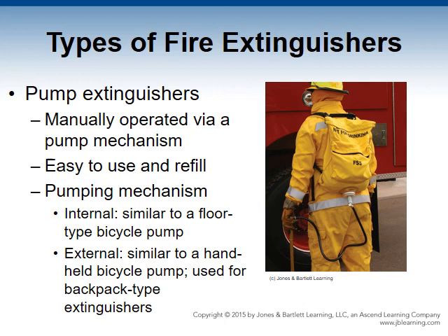Pump extinguishers are manually operated via a pump mechanism, which creates pressure in the tank allowing the water agent to be expelled. These extinguishers are easy to use and refill; the most important factor is keeping water in the tank. They usually have a capacity between 2.5 and 5 gallons. The pumping mechanism may be internal — immersed in the water tank, where each stroke pumps water through the hose — or external, similar to a handheld bicycle pump, common in backpack-type extinguishers used in rural and wilderness areas.